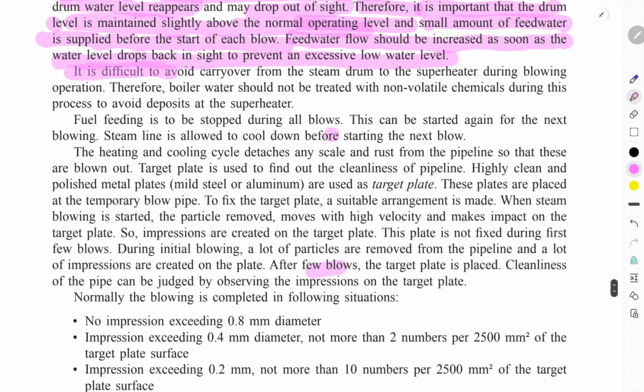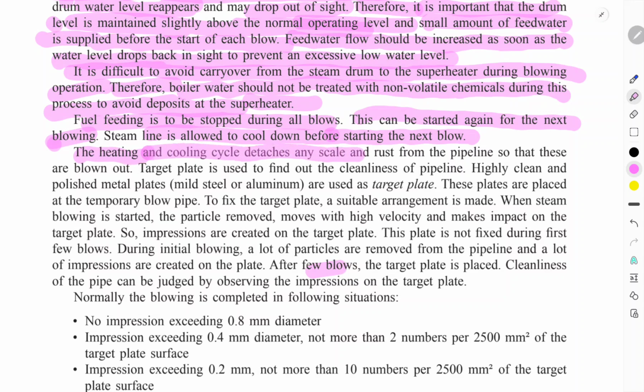It is difficult to avoid carryover from the steam drum to the superheater during the blowing operation. Therefore, the water should not be treated with non-volatile chemicals during the process, to avoid deposits in the superheater. The fuel feeding is to be stopped during the blowing, and started again for the next blowing. The steam line is allowed to cool down before the next blowing. The heating and cooling cycle detaches any scale and rust from the pipeline, so these are blown out.